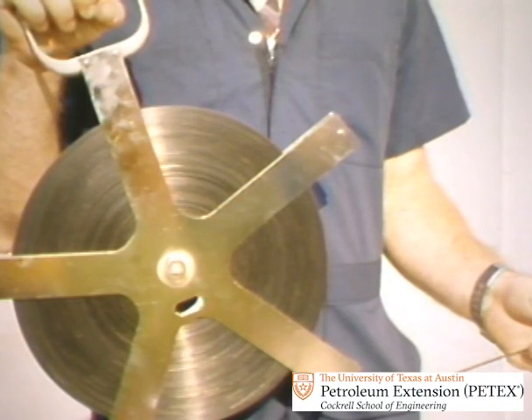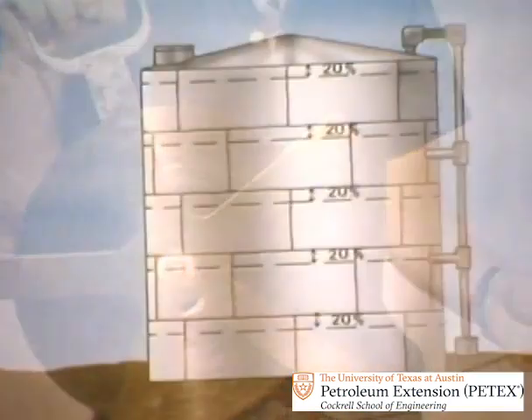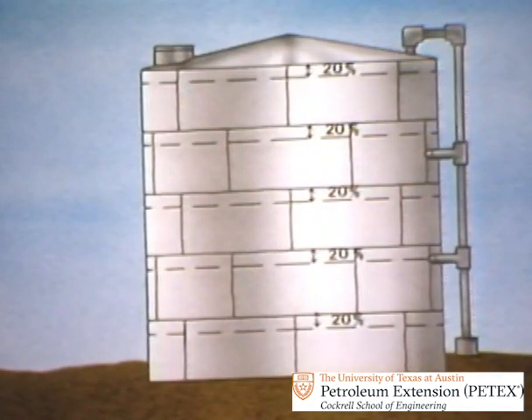They'll put a steel tape measure, a strapping tape, around each of the rings to measure their circumference. But they know that where they place the tape on the ring is critical. It's critical because API says the circumference of each ring should be measured at a distance equal to 20% of the ring width measured downward from the top.